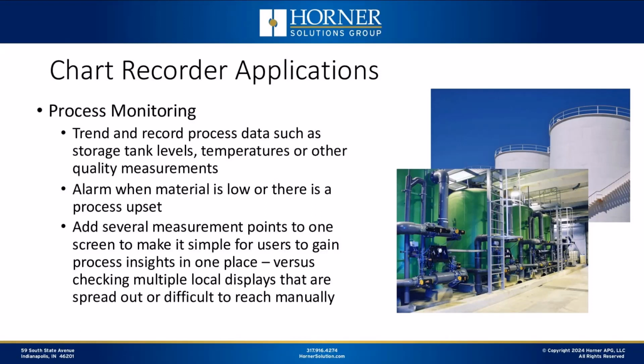And then another scenario that I hear mentioned a few times is, in some facilities where they might have 2 or 3 key process parameters that need to be monitored, by running those signals into a single device where they can easily monitor and record values, it's a lot easier than having a maintenance person navigate through the facility and crawl down into the crawl space or up into the attic or something to look at a specific gauge on an instrument to try and see what's going on. Having it all centrally located and logged in one location could be pretty convenient.